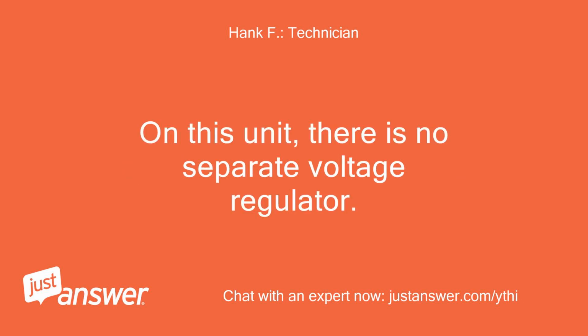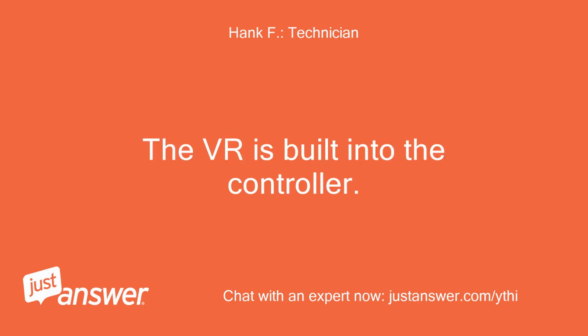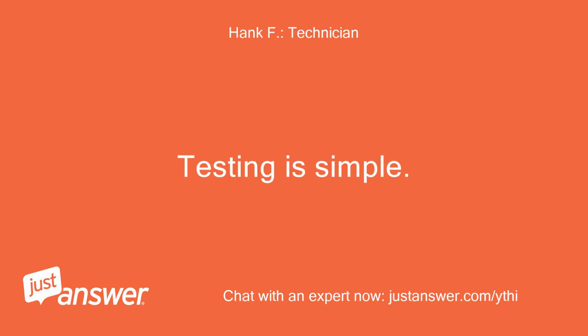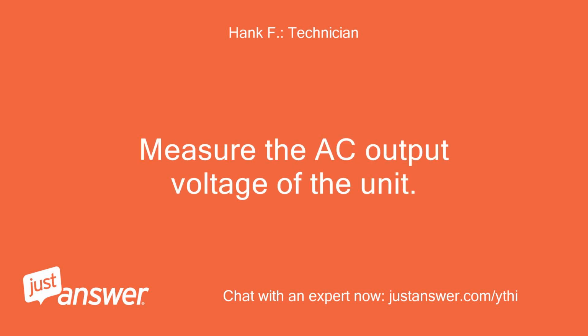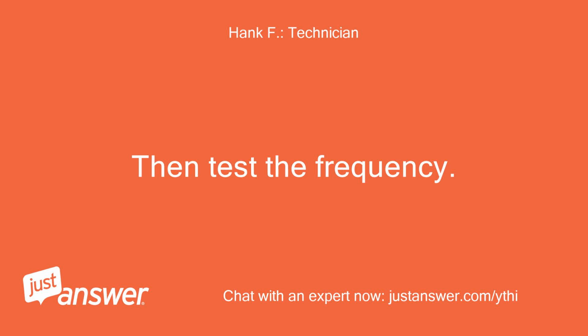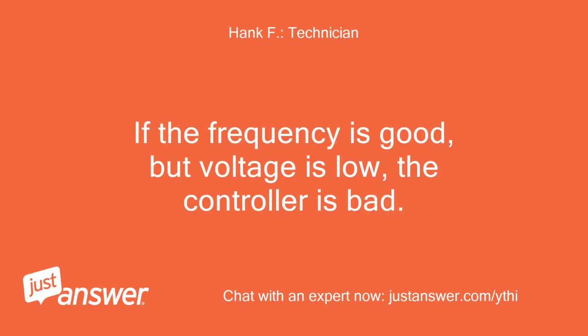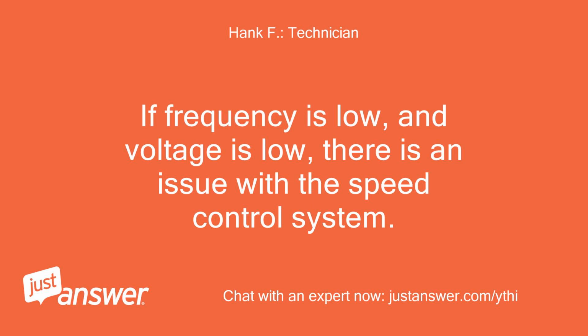On this unit, there is no separate voltage regulator. The VR is built into the controller. Testing is simple. Measure the AC output voltage of the unit. Then test the frequency. If the frequency is good, but voltage is low, the controller is bad. If frequency is low and voltage is low, there is an issue with the speed control system.